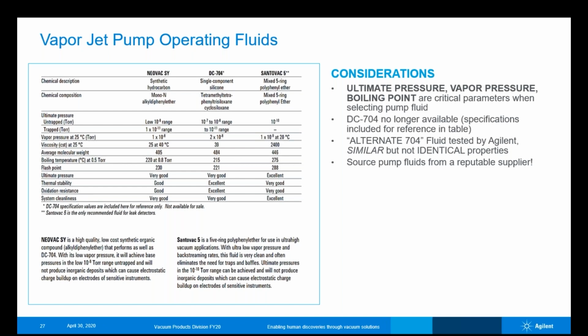There's an alternate 704 that our guys in our factory in Boston had looked at and evaluated against Dow Corning 704 and found it was pretty close, but not exactly the same as the DC 704 was. So again, you really need to be careful, and I can't stress enough to choose fluids from a reputable supplier.